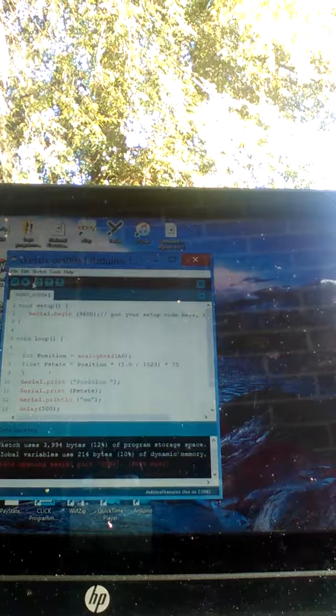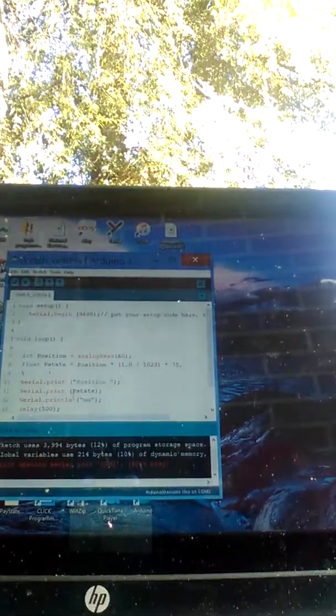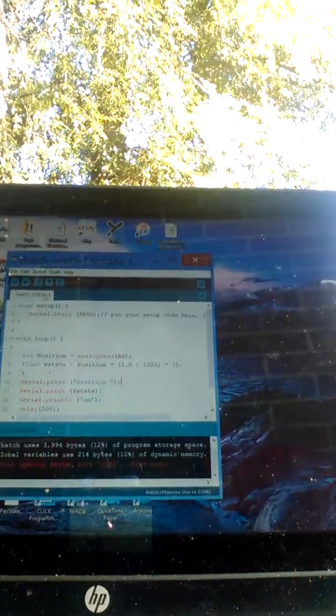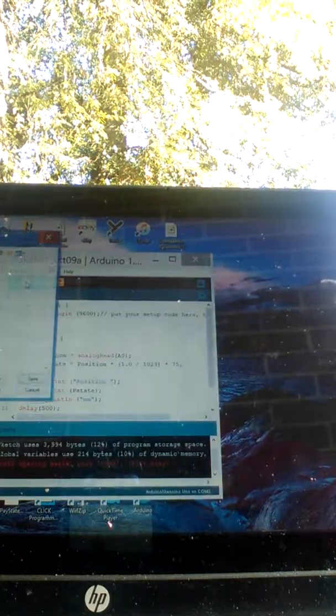Well, it looks like we need another algorithm. So what I'm going to do is multiply this function, because that's putting me in negative or under 0. So I'm going to multiply this again times 75 millimeters, the entire 75. Instead of giving me a maximum number of 1, I want to multiply that so I get a maximum number of 75, which is how big the transducer is. So let's upload that.